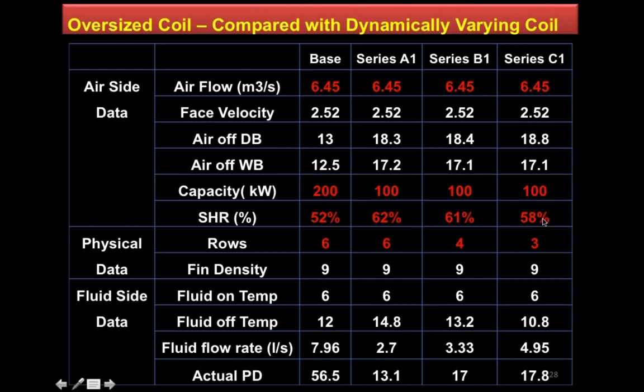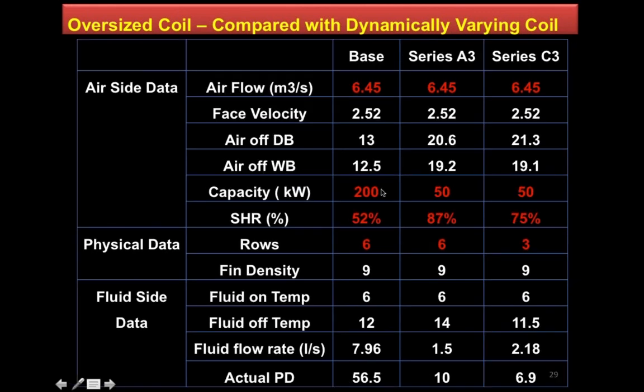significant drop. In fact, this becomes more obvious when I try to look at the part load conditions. Here I have the same 200 kilowatts oversized coil, the same large coil for the part load 50 kilowatts operation. Look at the very, very high sensible heat ratio. In other words, the humidity control is pretty poor. And then I change that to a 3-row deep coil. I can bring it down to about 75%. In other words, we're talking about a relative comparison.